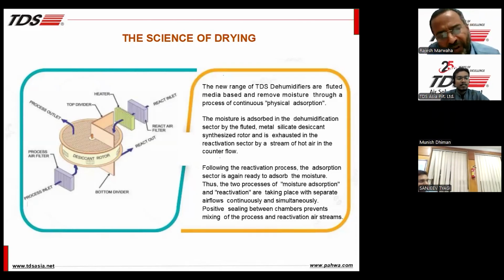And if I am from the bottom, if I am taking air at 90% or 95% RH, then process outlet will be around about 25% RH. That means I can absorb 75% of moisture from any area, because that is low vapor, totally dry air, which has the highest efficiency for absorbing the moisture. Now, this system has got a top divider, and heaters are also installed on the reactivation outlet system. And when the dry air goes inside the area which is to be dried, the temperature is a little bit increased, around about 4 to 5 degrees.